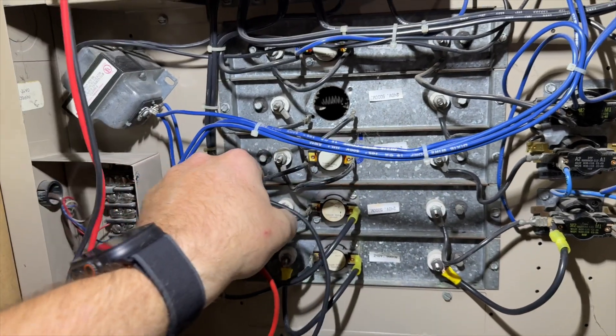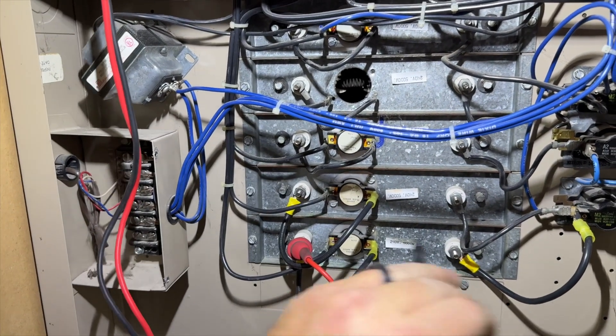And by doing this we're bypassing the high limits. You can see that there's one missing; that's because I already checked them and we have one that's closed.